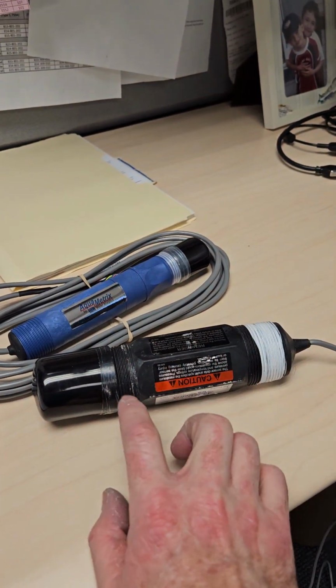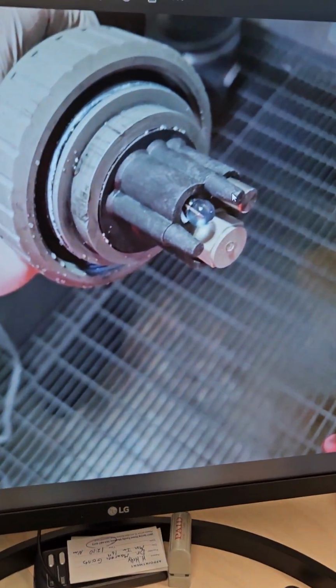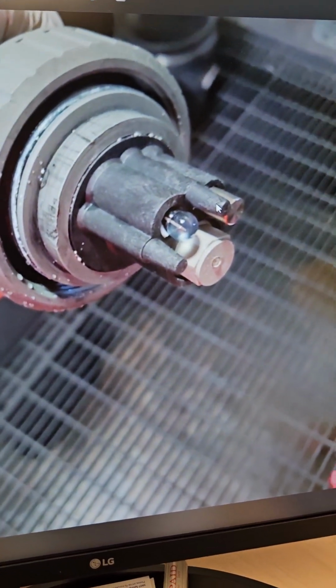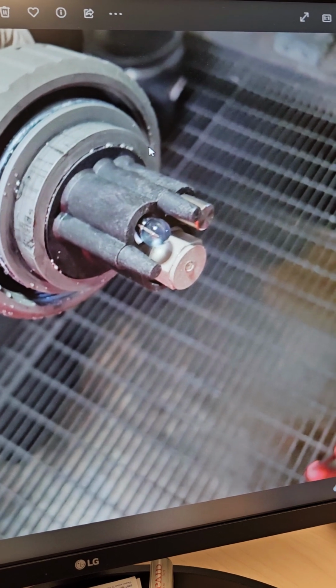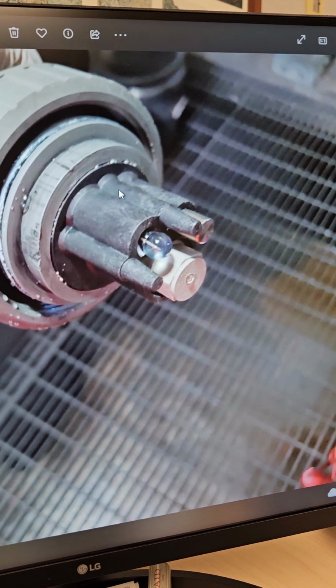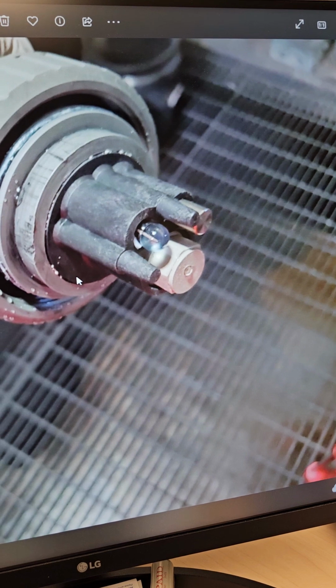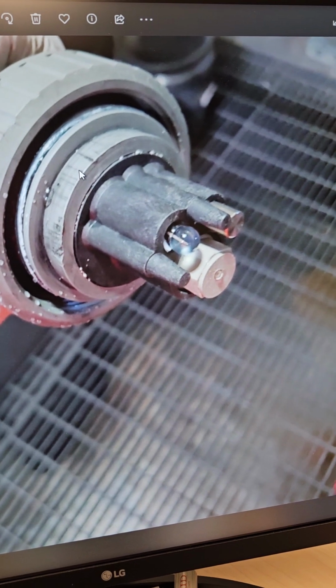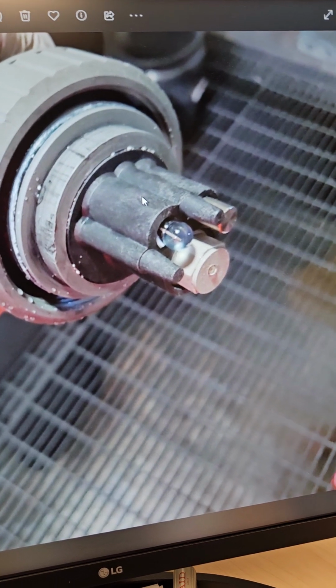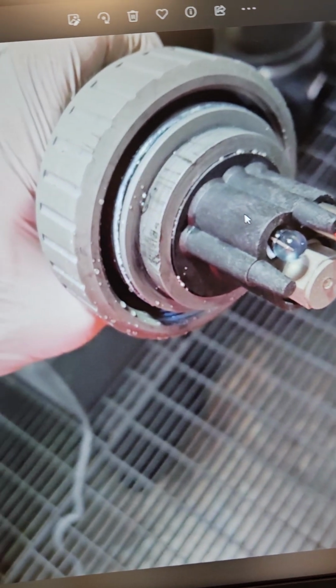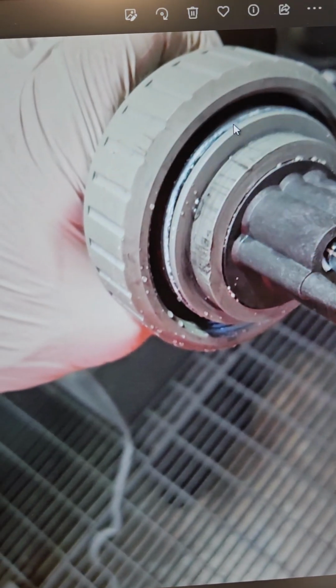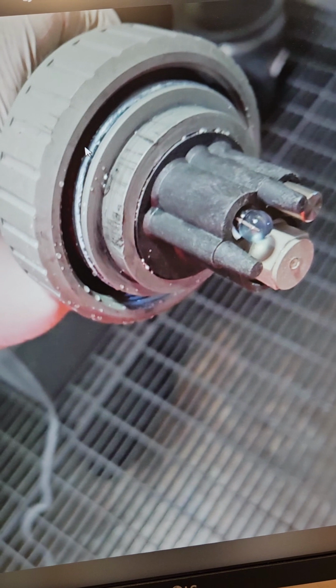If you're using a SensorX probe, they have a much newer mold, and those are much sharper threads. They're straight threads, so they kind of bottom out. They don't really have much taper. So you can try pipe dope and tape, it just doesn't ever work. I just prefer to put the RTV silicone on and turn this on carefully to the bottom, and it stops the leak. But as you can see, those O-rings in there basically seal until air can get in here.